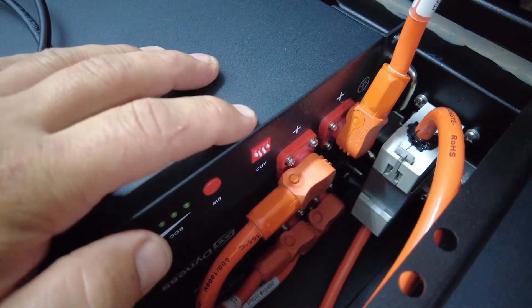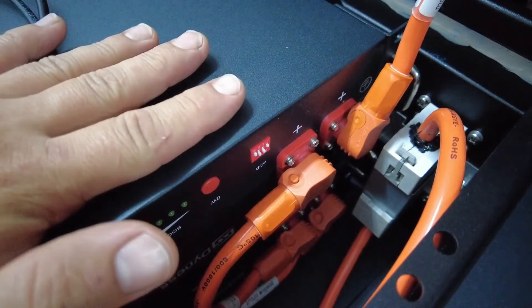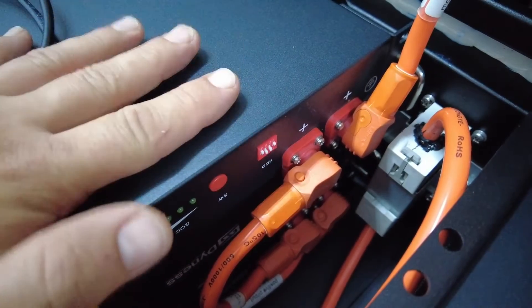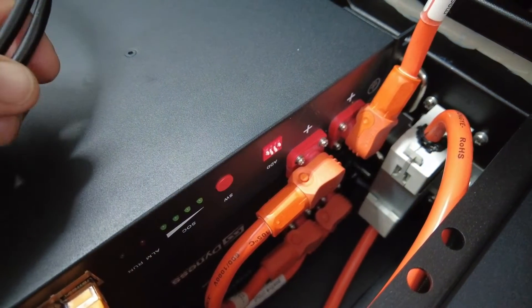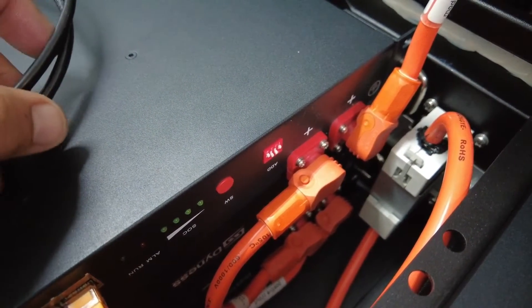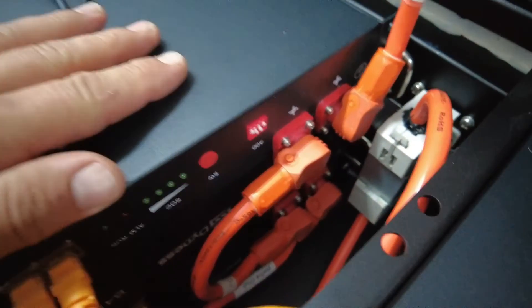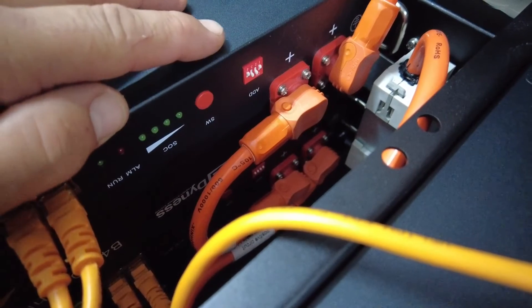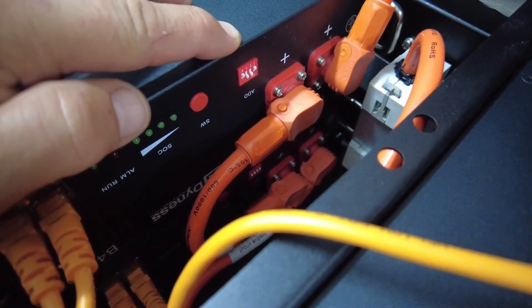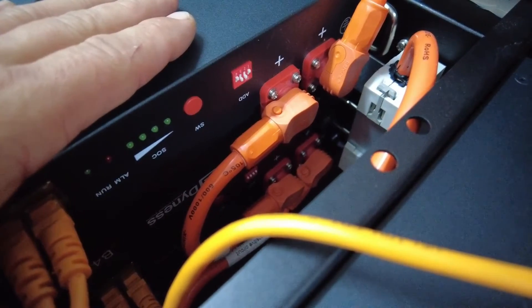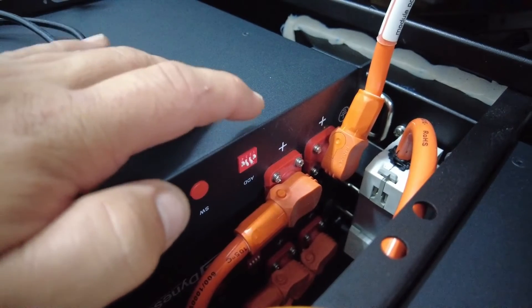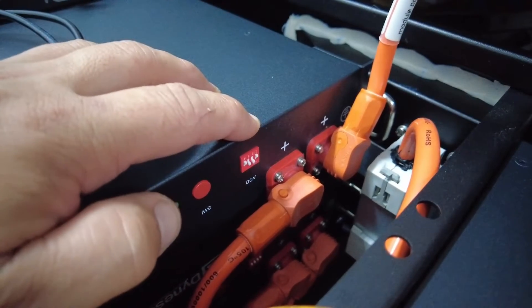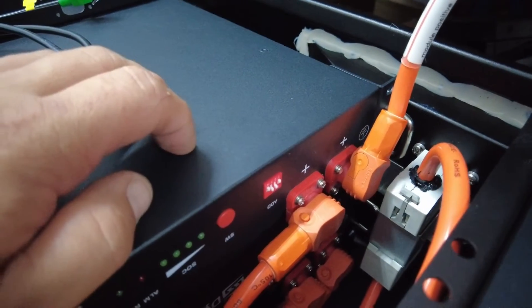The 0110 dip setting is only assigned to the master battery. The master battery is the battery connected to the inverter communication for BMS. All of the remaining modules will have the dip settings in the off position. All four dips need to be off on all three slave batteries. It is only the master battery that has the 0110 dip setting assigned to it.